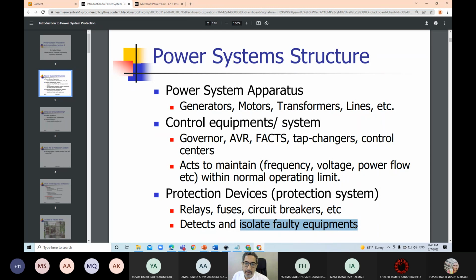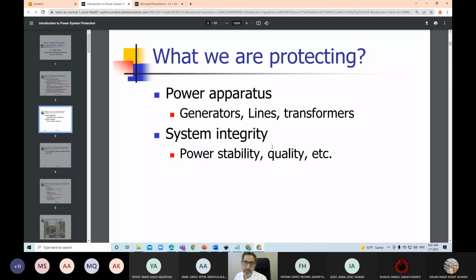And as I said, what we are protecting are the power system components in the power systems: generators, lines, transformers, motors, and we are also trying to maintain system integrity. We want to make systems stable by acting so fast to disconnect the faulty equipment. If the action of the protection function is slow, it might lead to a system blackout. Okay.